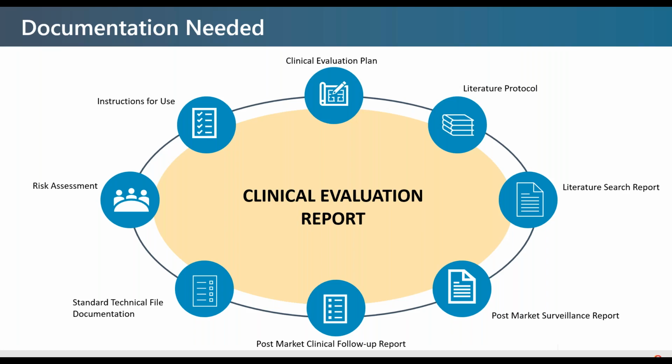And then finally, especially if this is your first one, you'll take the findings of the clinical evaluation report and come up with your PMCF plan. If it's not your first report, you should hopefully have a PMCF report that is feeding into your clinical evaluation report, and you're going to present those findings.